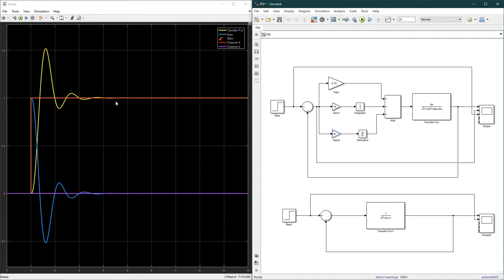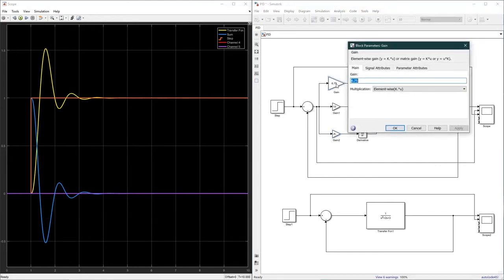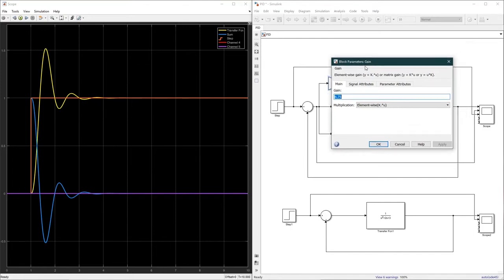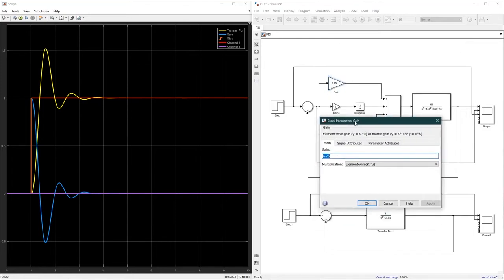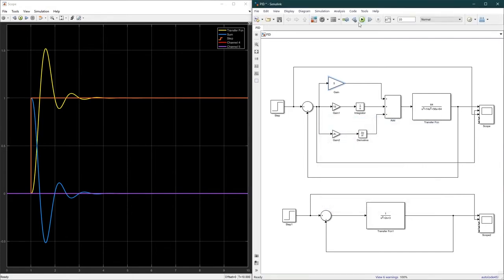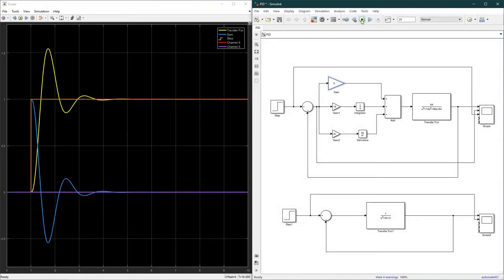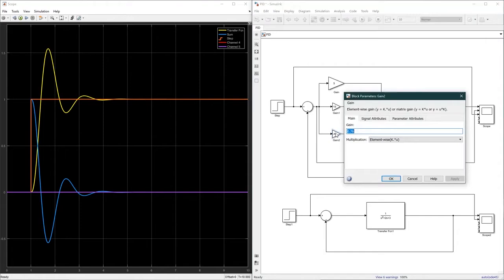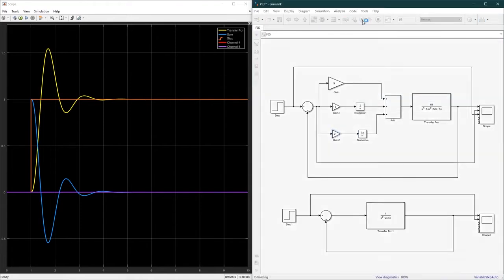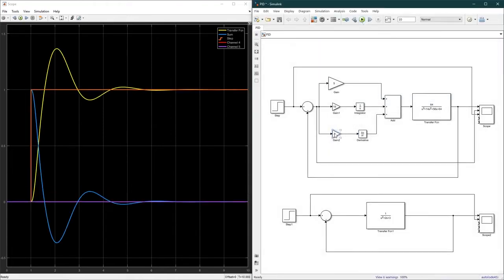Okay, next let's adjust PID manually for proper values. If it has an overshoot like this, what do we have to do? Yes, decrease Kp. There is still some overshoot, so add some more Kd. Overshoot is lower.